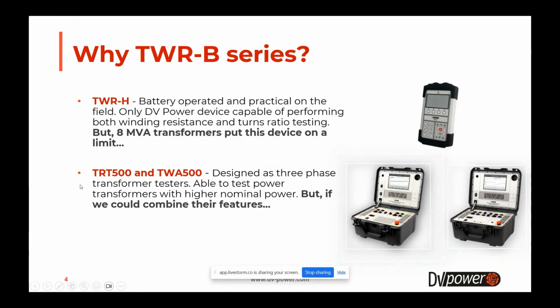As you can probably see on this slide, we use a combination of hardware-wise similar devices for winding resistance measurement and for turns ratio measurement, but we now decided to combine these 2 devices into one, enable both features of both devices, and on top of that include battery power. So we tried to produce a new device which will be able to combine the main features of our most improved transformer testing devices.